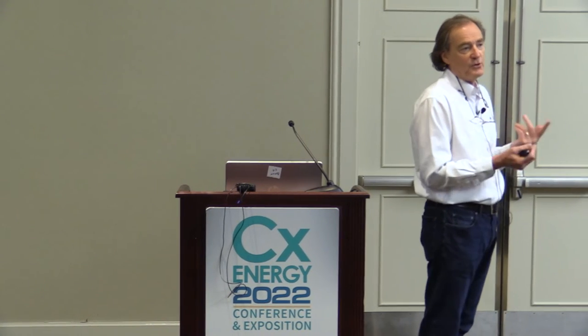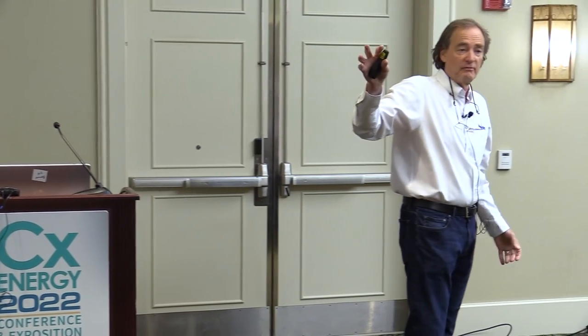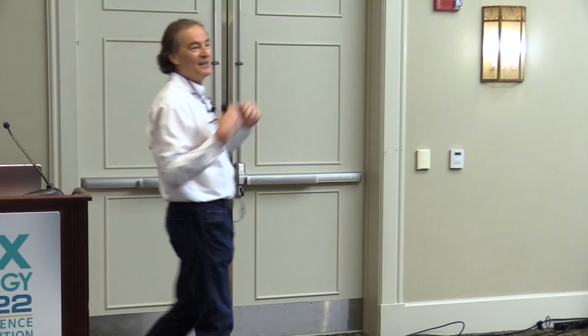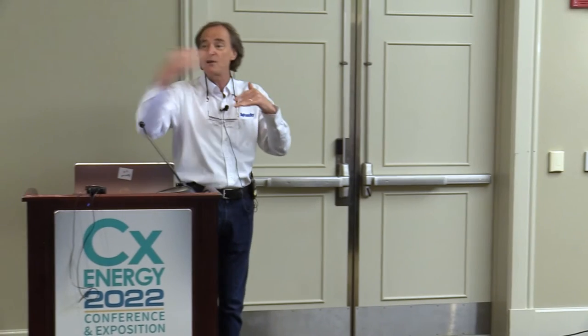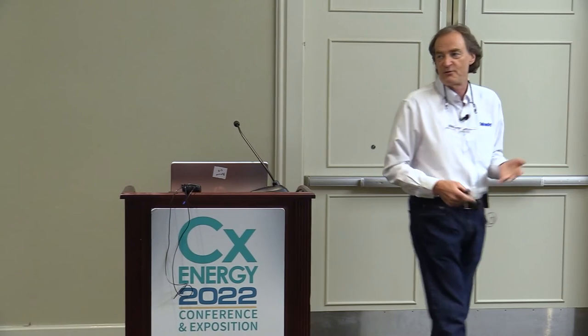The interesting thing about benchmarks is that usually there's a benchmark for a certain type of building. We're seeing an increased use of taking the energy model information, what the building design is expected to perform, and using that as a benchmark or a baseline, because the goal we want to see is: are we meeting the design, or how far off of the design are we? So the model data, which is an output with charts and graphs, can be brought into the analytics software and compared to the actual, which is coming from meters, submeters, smart meters, and web service feeds from utility companies. You get the idea. A lot of different data sources.